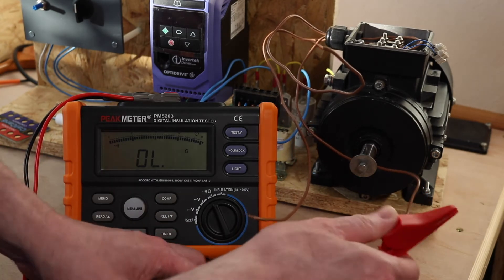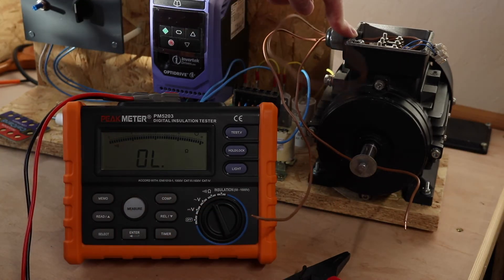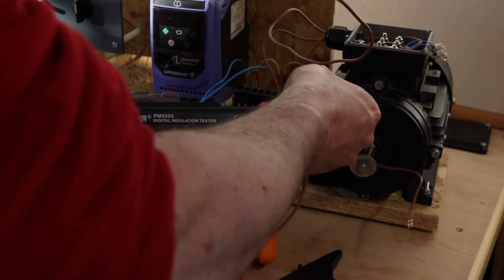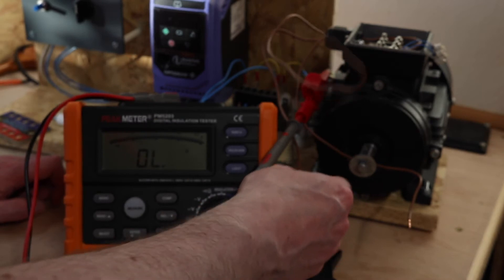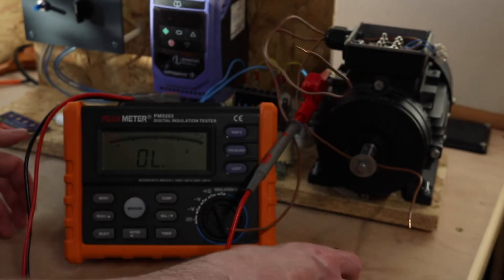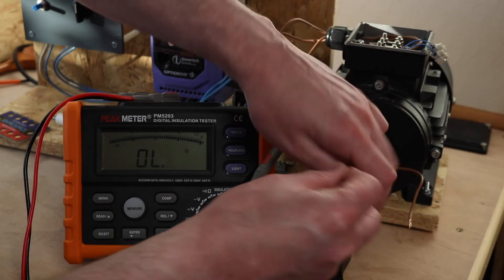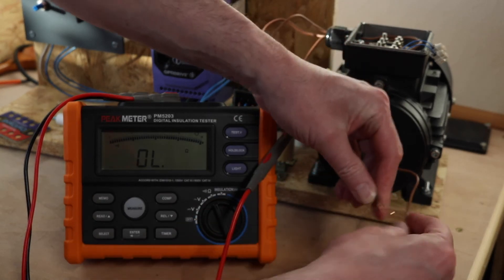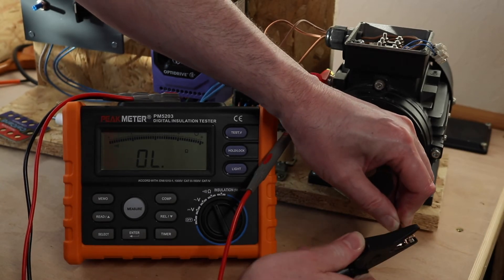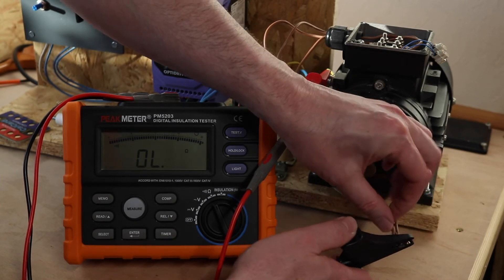Now we move on to an insulation test. For this particular motor, just because it's wired in Delta configuration and I've got combined windings in there, it's just going to be one test that I do. One probe onto the earth and then the other I'm going to link these three phase wires together, get the croc around them as one.